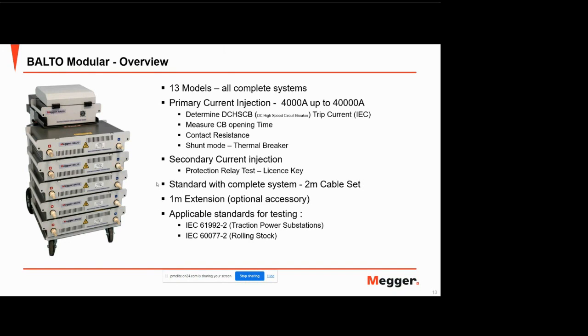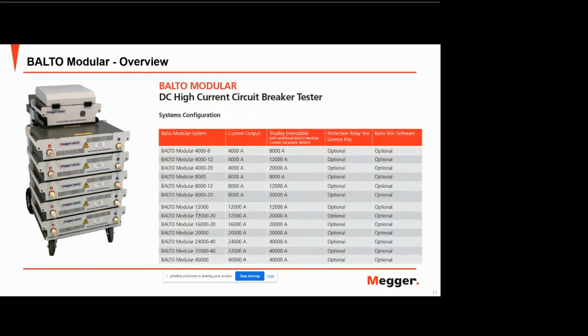As I said, the Balto modular comes as a complete system, so you'll get your 2-meter standard cable set. We do have other cable sets for extension. These are accessories. And as we've said previously, Balto modular is compliant to both 61992 and 60077 for the 200 amps per microsecond reduced rate of rise for the current. Okay, so that's modular. So if you have the data sheet, you can see on there exactly what each of the systems that we offer actually offer.